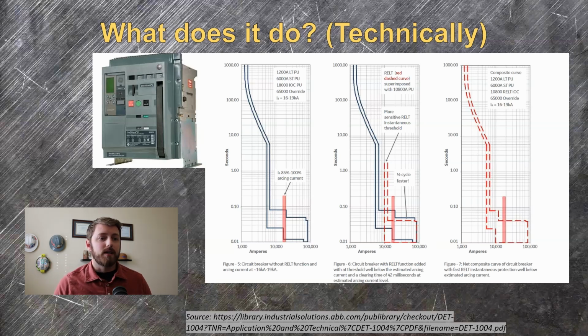Often these maintenance mode settings simply bring the instantaneous setting down to the minimum of 2 or 3 times the frame rating. For this breaker, that would be 2400 amps. This can cause the system to be incorrectly coordinated. Certain high inrush loads may now trip the main instead of the corresponding feeder breakers. Obviously, that's unacceptable under normal load conditions or normal operating conditions, but it's a worthwhile risk if you're going to be face first in open, energized switchgear during an IR scan.